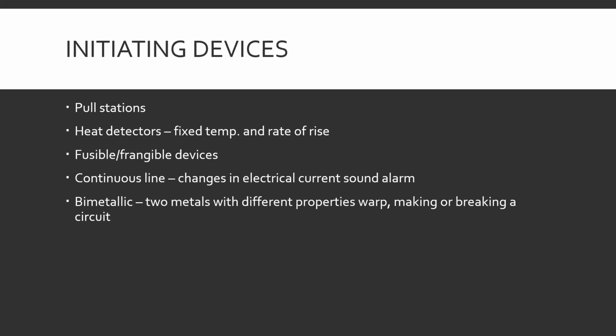Those systems can get fooled if they're near a door. If it's negative 20 out because it's the middle of winter up north, and it's a nice toasty 65 degrees inside, and someone opens the door and all of a sudden the temperature drops or rises or does something crazy, that can cause it to go off because it thinks, whoa, temperature changed really quickly, I gotta go off. Fusible frangible devices, I know those are later, but those are like your sprinkler heads. We're going to leave that at that for now.